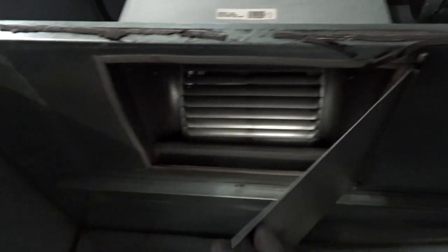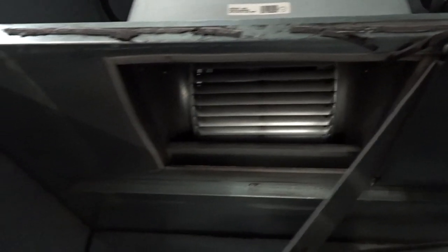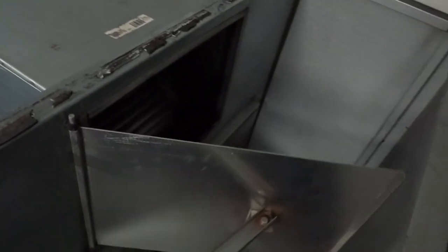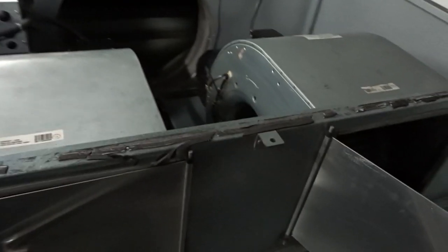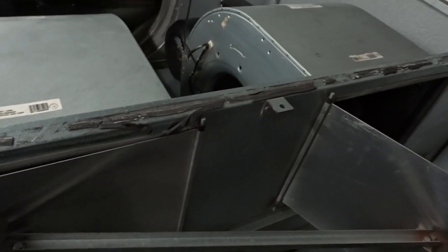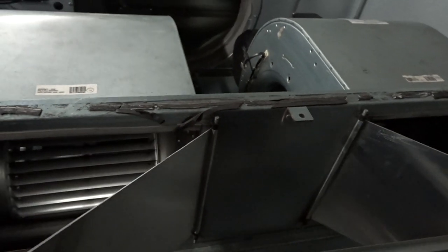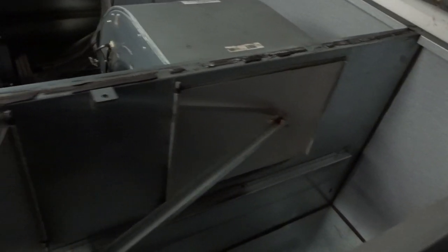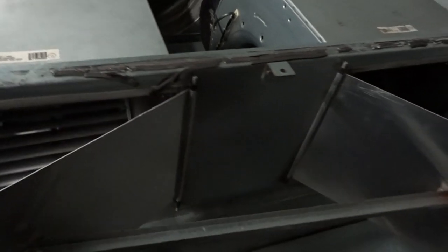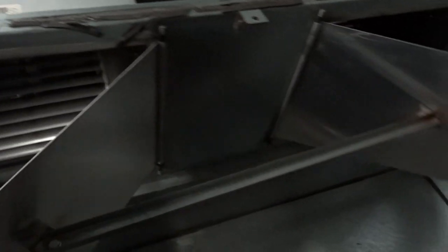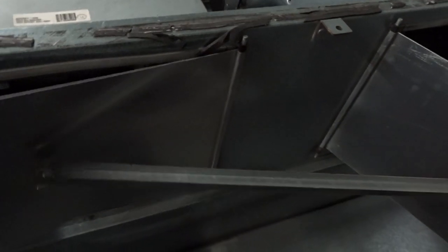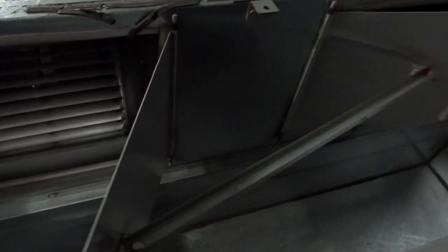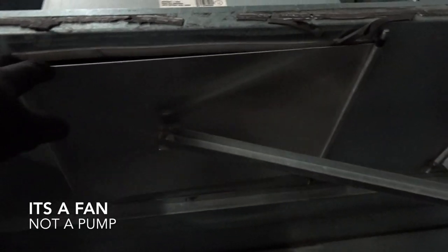And here we have the duct doors. So when Fan 1 is running, this will open up and allow the air through. When Fan 1 shifts over, Fan 2 will start up and as that starts up this will open and that door there will close. There's no electrical components to this operation, it's all manual. So it does it itself basically. When the flow goes through whichever pump, it will open the correct door for that pump.